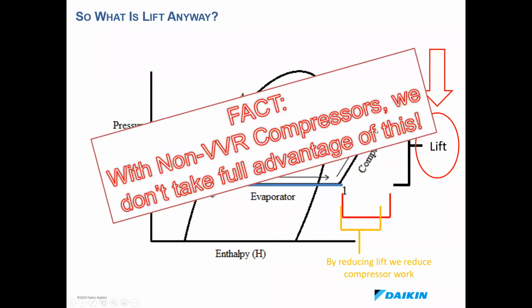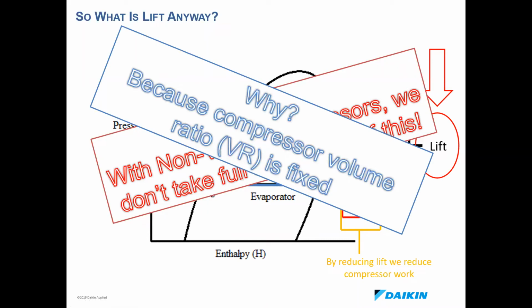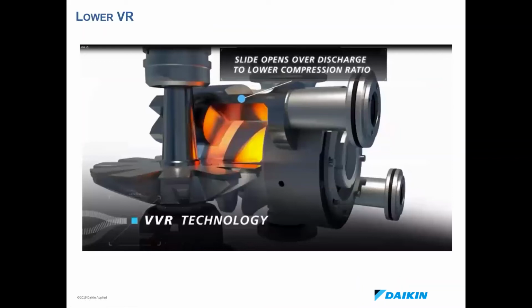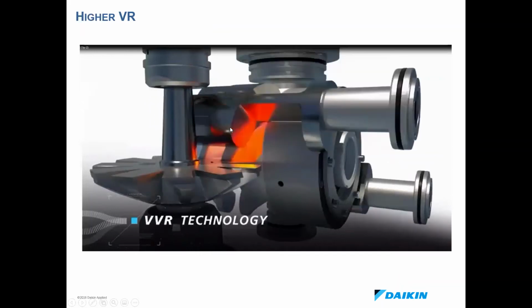You can't do this without VVR compressors because the volume ratio is fixed. You wouldn't be able to vary your volume ratio or your compression ratio along the screw. So with that being said, here's just what it kind of looks like. This is what a lower volume ratio looks like. The refrigerant is coming in from the left side, moving to the right. It's able to escape the flute of the screw earlier in a lower volume ratio scenario, whereas in a higher volume ratio scenario or a higher lift scenario, the discharge valve will move towards the discharge side of the screw, which would make the refrigerant escape later, thus compressing it further.